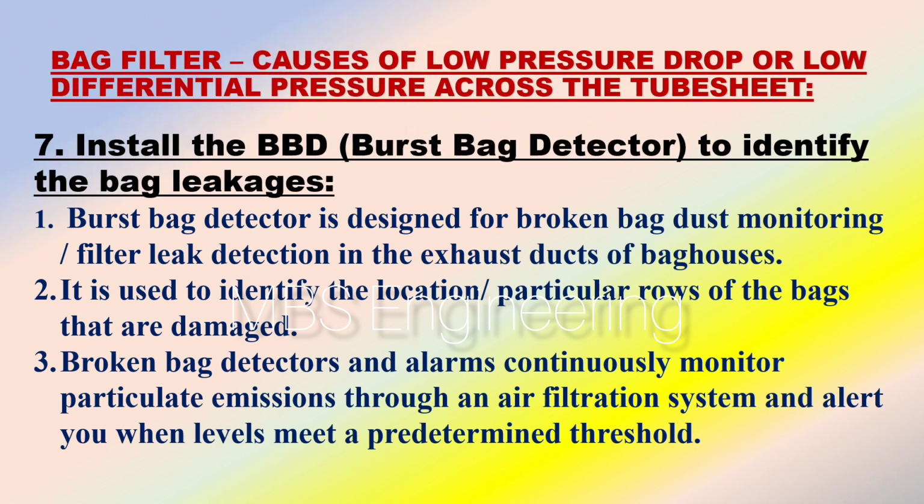One of the main causes of low differential pressure is not installing the BBD, burst bag detector, in the filter bags. It is recommended to install the burst bag detector to identify the leakages easily. Point number 1. A burst bag detector is designed for broken bag dust monitoring, filter leak detection in the exhaust ducts of baghouses. Point number 2. It is used to identify the location, particular rows of the bags that are damaged. Point number 3. Broken bag detectors and alarms continuously monitor particulate emissions through an air filtration system and alert you when levels meet a predetermined threshold.